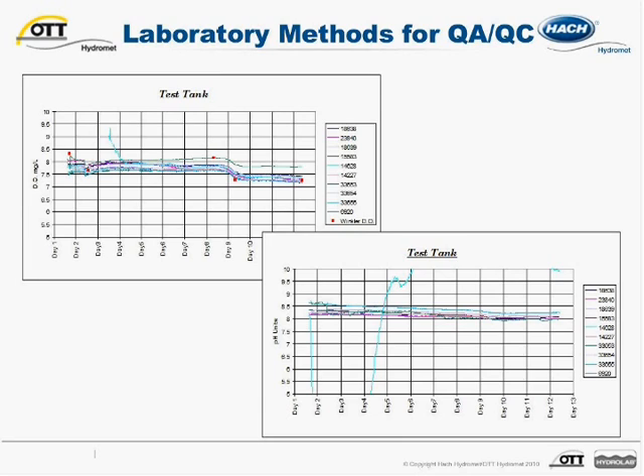Here are dissolved oxygen data from the same lab tank test. QA/QC is a paired Winkler titration for dissolved oxygen. There is some variation evident within the group. Here you can ask yourself whether this variation is acceptable for your program. Something to investigate is the consistency of the Winklers. Whether these data are from a Clark cell DO sensor or an optical sensor — the answer to this may provide clues for troubleshooting if data are from a Clark cell.